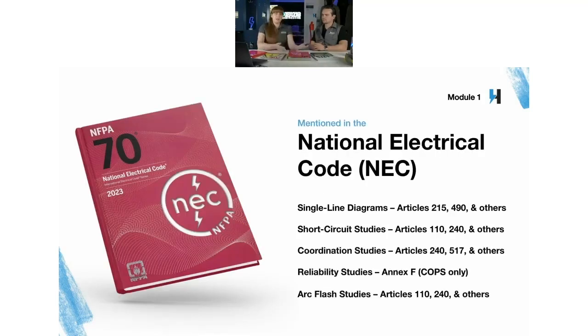For the National Electrical Code, it also starts out pointing out that it needs a single line diagram for your system, but then there's also arc flash - 110.16 talks about arc flash. But then we see there are 3 additional things that the 70E doesn't necessarily mention. What are those? We've got short circuit studies mentioned in Chapter 1 of the NEC. It's a pretty big one, general requirements, and that shows up quite a bit all over the NEC.